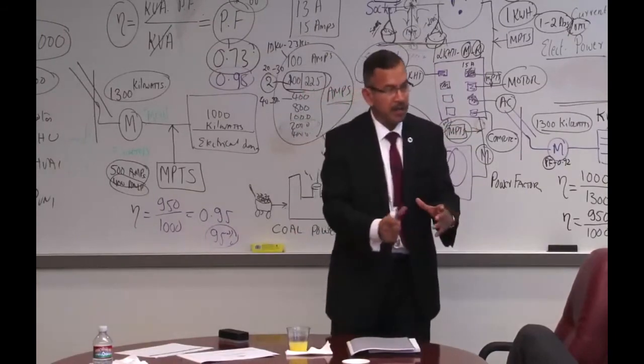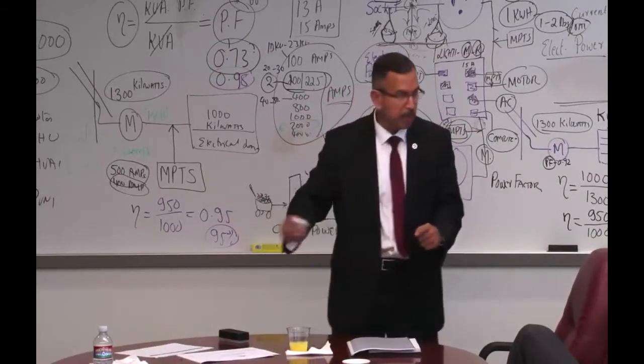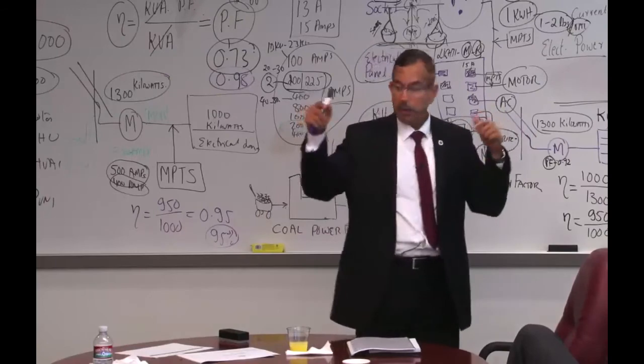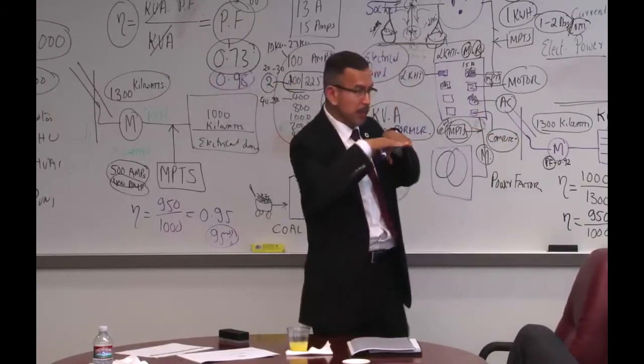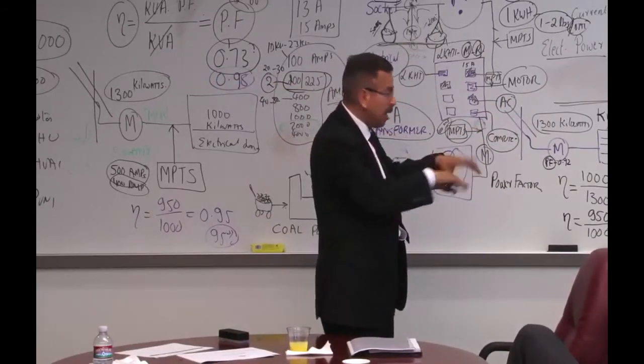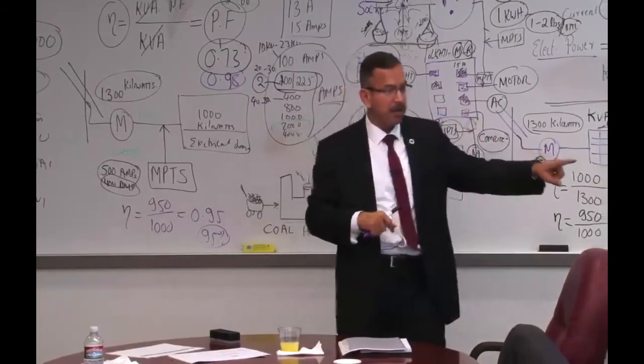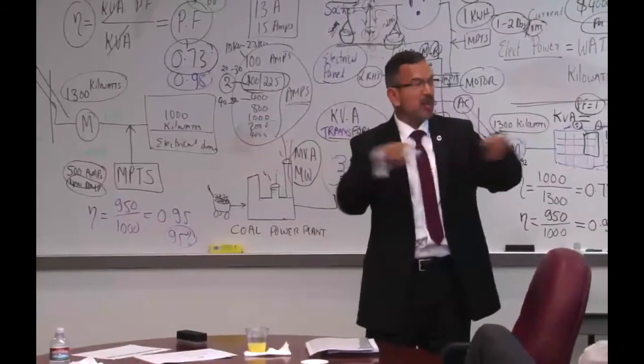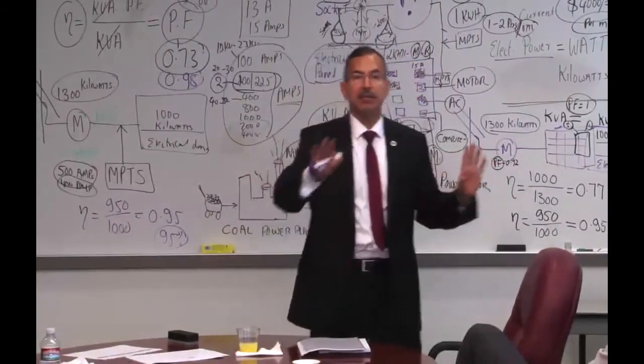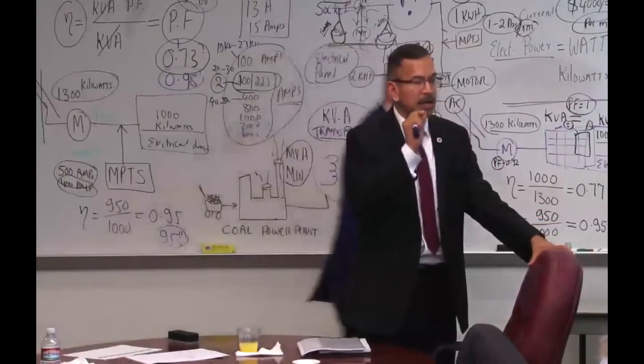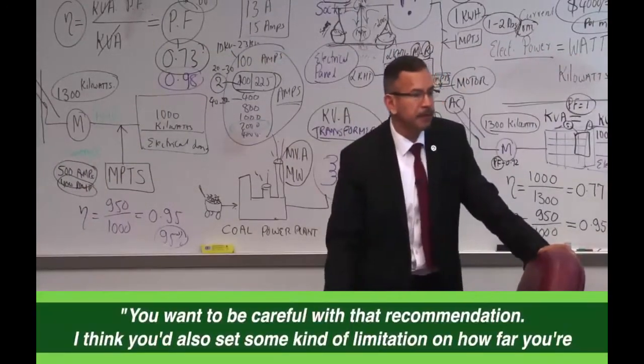Rectifiers send out harmonics upstream or downstream. When those harmonics are fed into the unit, the electronic network can get into resonance. I'm getting into a technical area, forget about it, we don't want that, but install it upstream - you want to be careful with that recommendation, I would think.